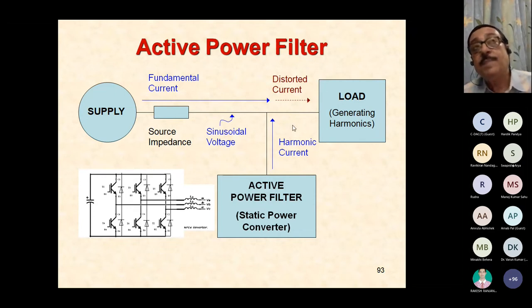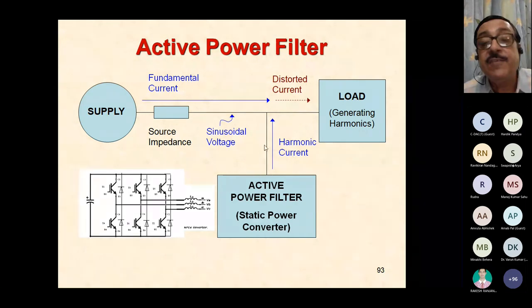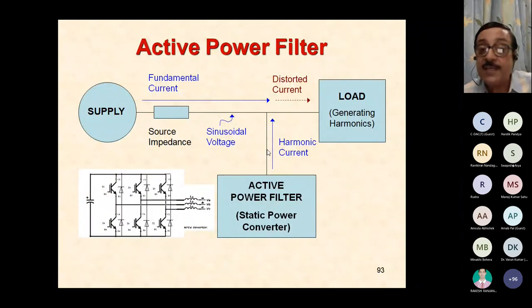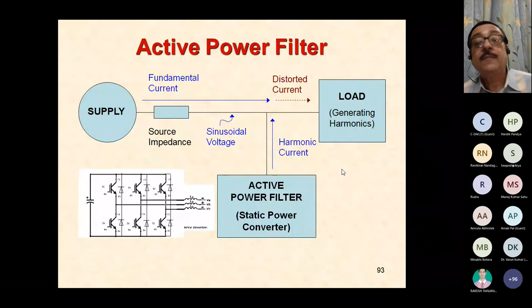And the benefit here over passive filters is you do not have any resonance problems, because you are not using any direct inductance or capacitor connected across the lines. Second thing is, you don't have to operate harmonic by harmonic, fifth, seventh individually, like in a passive filter. Here you can have the composite harmonic distorted waveform as the template, and you can inject the same distorted template current here. You don't have to find out exactly which is how much. Composite template will do. So you monitor the total current, subtract the fundamental, whatever is the remaining shall be your template here, and it keeps operating.